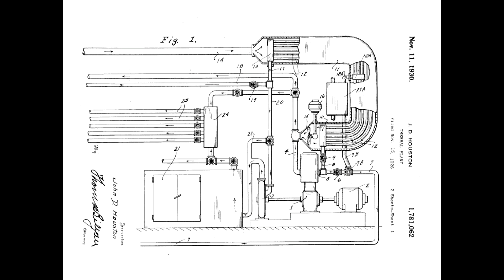Then the compressed air comes out of here, comes back down through the air motor, which is on a common shaft. So the air motor then expands the air that comes out after the heat's taken out, and the mechanical energy produced here relieves the motor of some of its load for running the compressor in the first place, and then the decompressed air is used to produce industrial refrigeration.